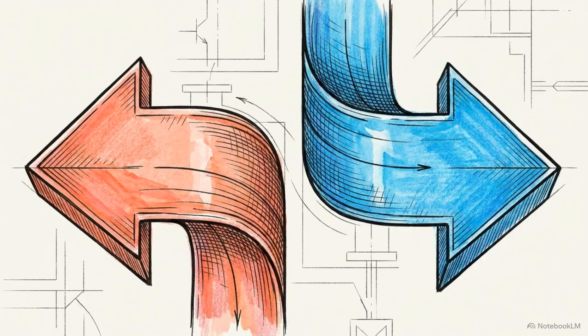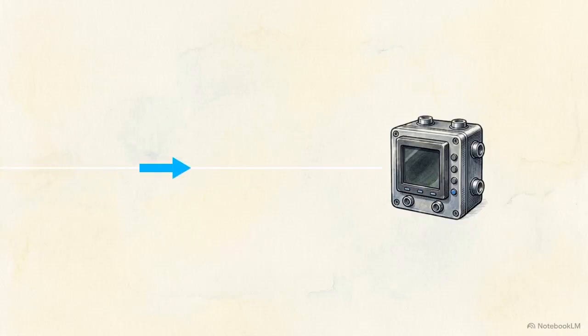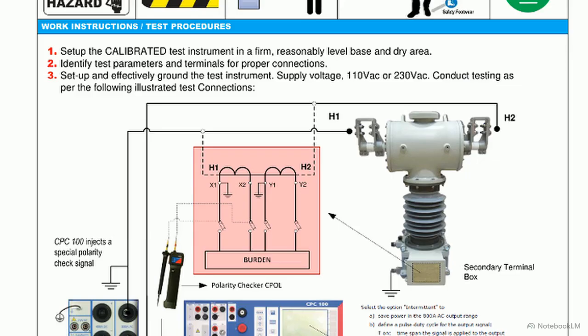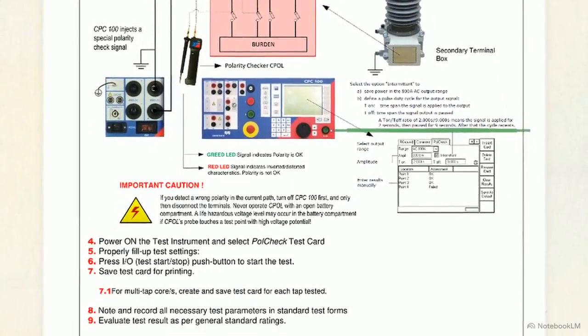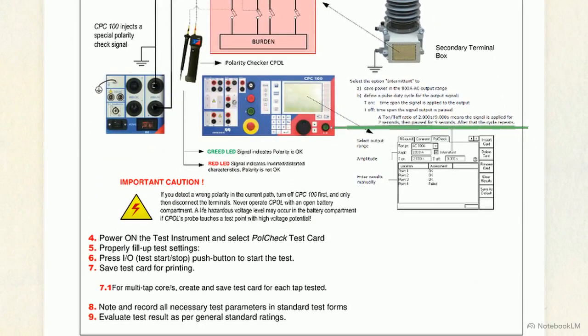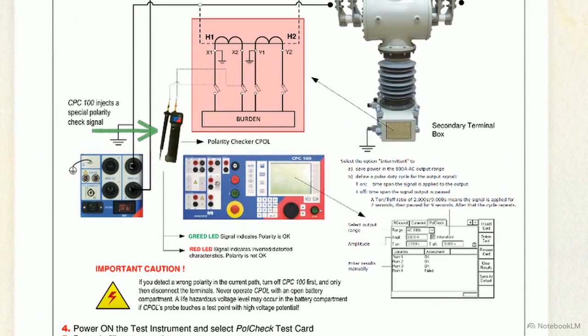We conclude the active testing phase with polarity and core direction. Physical integrity is useless if the secondary signal is flowing in the wrong logical direction. To verify orientation, the CPC-100 injects a specialized asymmetrical sawtooth signal directly into the primary H1 path. To conserve power, this signal is applied on an intermittent duty cycle. The instrument pulses the signal for 2 seconds, pauses for 9 seconds, and repeats. Out at the secondary terminal block, the field technician uses a handheld CPOL polarity checker. This device reads the waveform signature of that asymmetrical pulse.